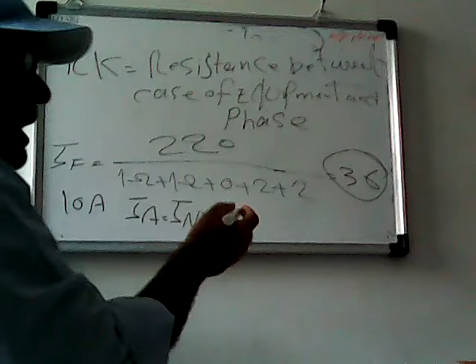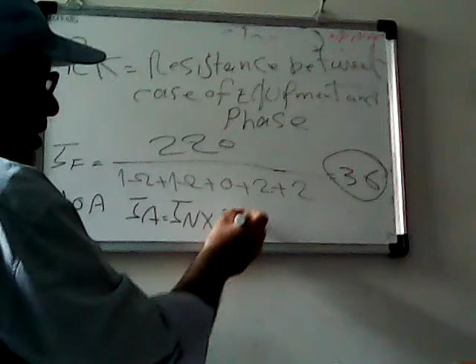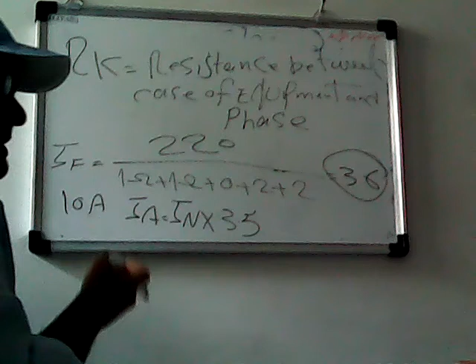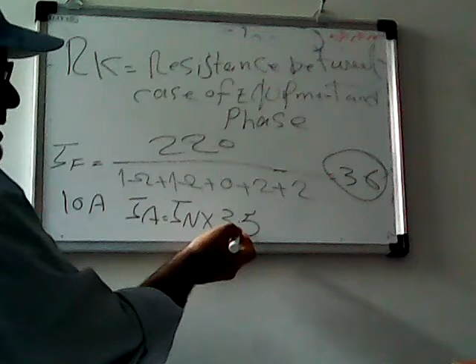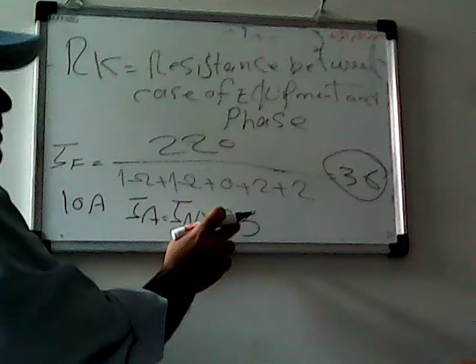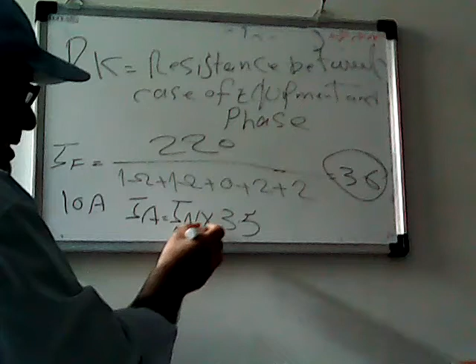We have IA, current in fuses, equal to I nominal current of fuses times the stable coefficient. Some coefficient of cut of fuse is 3.5, some is 2.5, some is 1.5. This depends on whether the fuse is rush-ag or low-ag. Here is low-ag. 10 times 3.5 is 35 ampere.